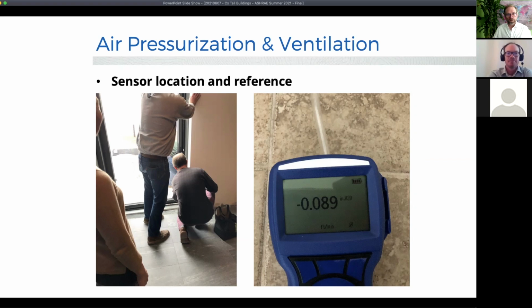So the location of the sensors, their reference point, and the seasonality all matter. A building in the summer in Chicago or a northern climate operates very differently than in the winter—the stack effect can flip and behave differently. We want to look at things seasonally, so when we commission these buildings, we don't just do it once. We commission multiple times under different temperature scenarios to understand how the systems will react and to help set up the program.